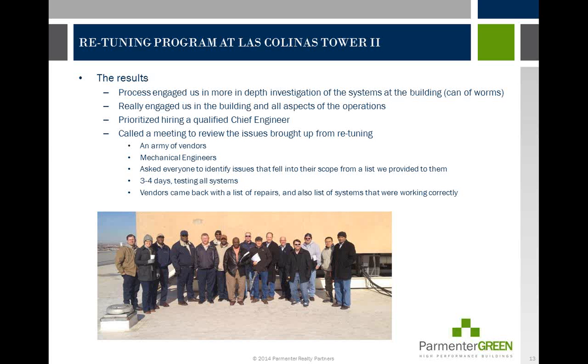We went through the building with a fine-tooth comb, and when we came back, we found valves that were inoperable, pneumatics that weren't working properly, and stopped-up filters. We weren't getting enough pneumatic air to the top of the building. There were all kinds of things we uncovered. They came back with a list of repairs, and we assigned each one the task of making the repairs so the building would operate properly.